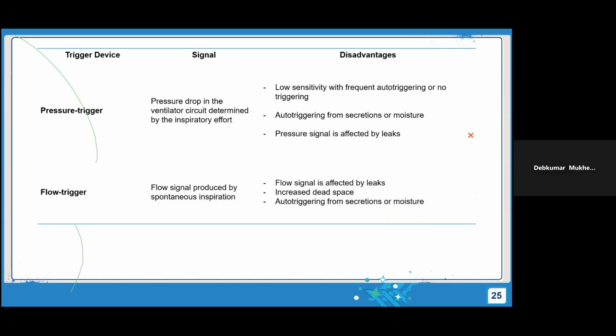So in the pressure trigger, what happens? The baby has to create a negative pressure, and all of you will agree with me that in a small preterm infant, the baby may not be able to create that much negative pressure to sense a breath. That is the problem of the pressure trigger, because we know from our first lecture that most babies may create minus 6 centimeter water pressure. So if the baby can create that much, minus 6 or minus 1 centimeter pressure, only then will the ventilator recognize the breath and deliver the breath. That is the problem of the pressure trigger, because most of the smallest preterm infants may not be able to produce that much negative pressure when connected with NIPPV.